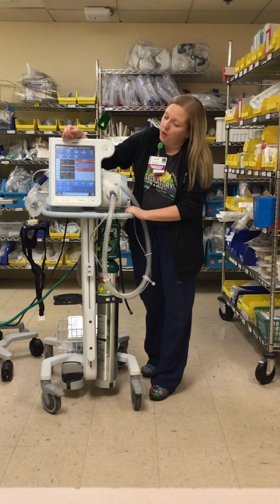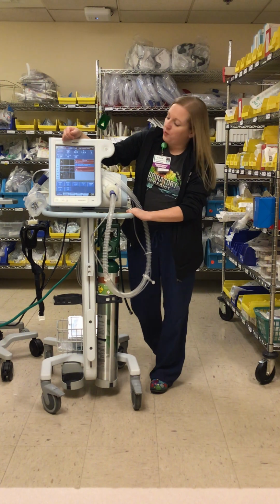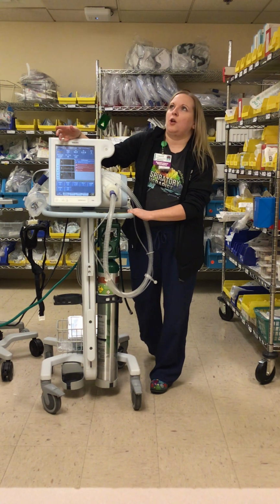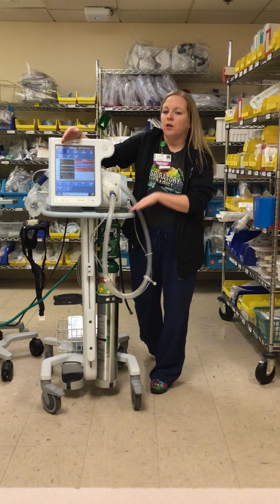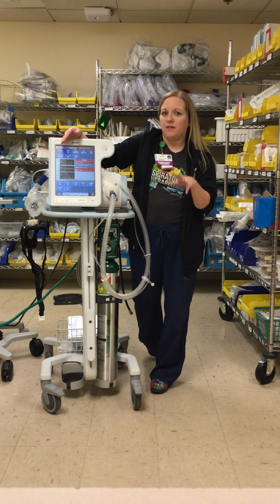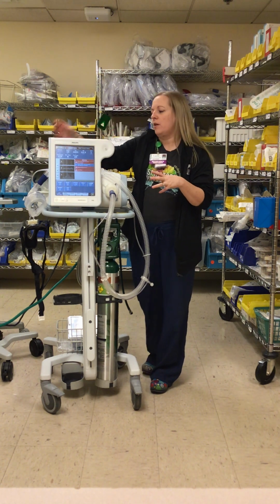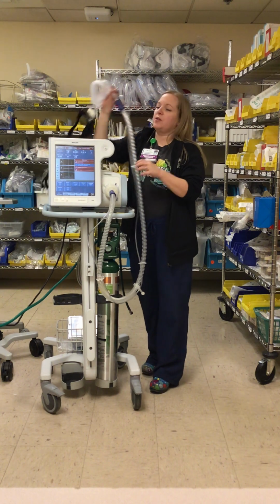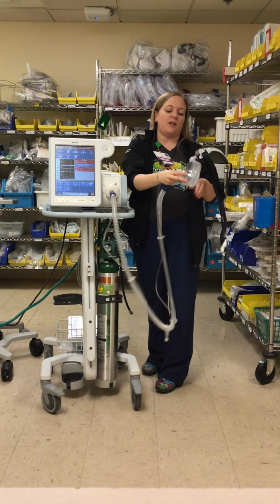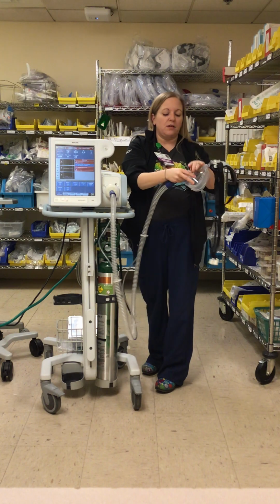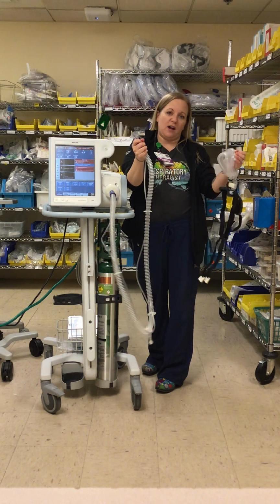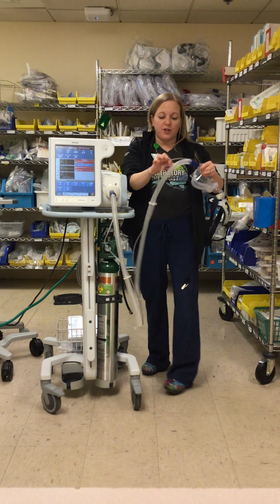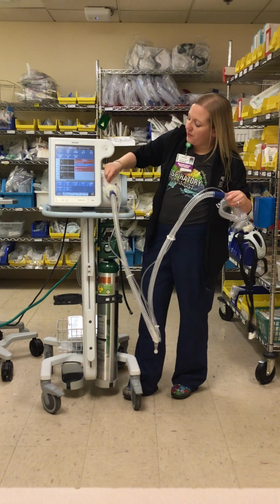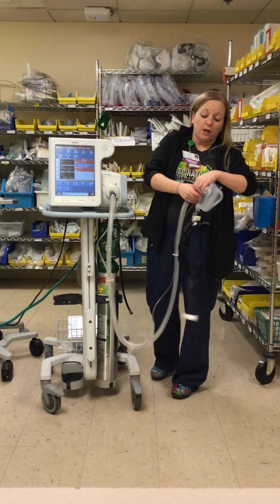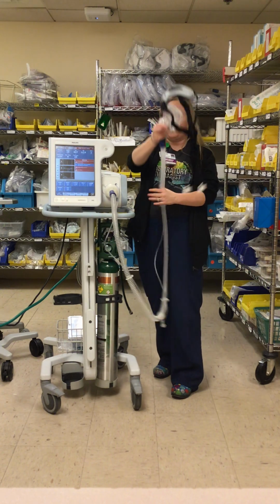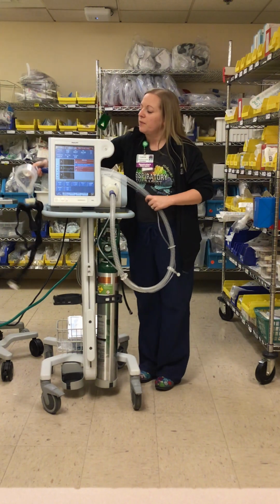Alarms. One of the alarms you will see the most is the patient disconnect, low minute ventilation, low tidal volume. All of those alarms indicate that there's something disconnected somewhere. So the first thing you want to do is start with the patient. You're going to check that the mask is fitted on their face. You're going to check that the circuit is not disconnected. And then you're going to check all your tubing to make sure everything is plugged in and closed. Of course, you can call your RT, but these are some troubleshooting things you can do until they get there.